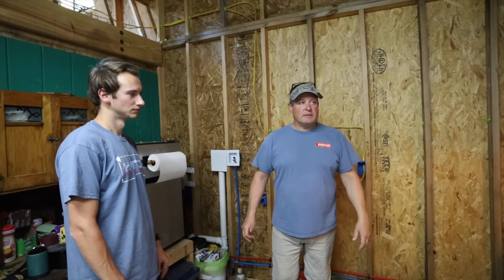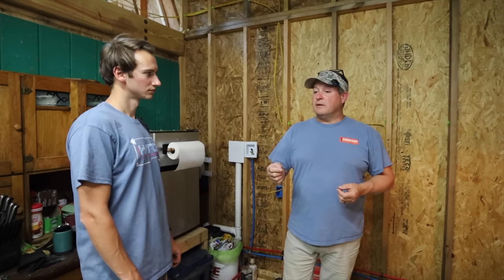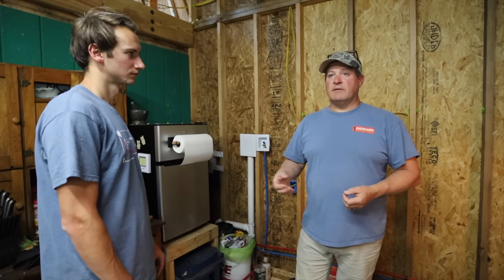We still have to bring another home run in here to pick up switches for the disposal and get your light off of it. I'm sure it's going to be an LED — and that's the neat thing now that all the lights are LEDs, you're not really burning a whole lot of power. We've got 14-gauge wire. So once you leave your switches, run 14 to your lights — you don't need to run your 12. You can even run plugs off 14. Everything's so efficient now that you can run 10 outlets on a 14 or 12 on a 20-amp circuit. The National Electric Code doesn't tell you you've got to be limited to a specific amount — it gives you a percentage, no more than 80% of the load on that circuit.